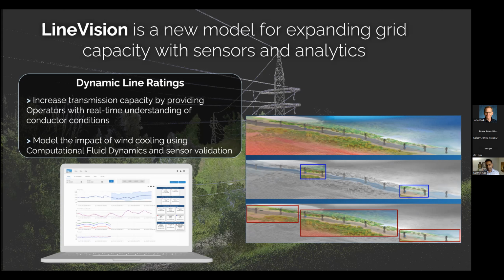What dynamic line ratings does is take real world, real-time conditions on that conductor and use it to calculate what the actual capacity is on the line at any given time. It turns out that it's actually the cooling effect of wind that's the single biggest driver of that capacity, so we can use our sensor data, looking at both the vertical and horizontal motion of the conductor, to figure out this hyperlocal wind speed.